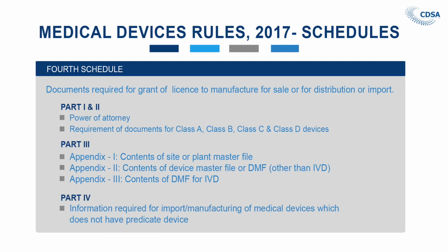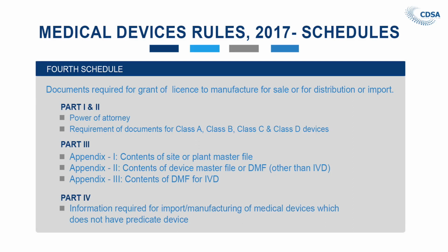What the plant master file contains is given in the Fourth Schedule, Part 3, Appendix 1. Appendix 2 is the content of the device master file for medical devices other than IVD. What content, what information, what technical document is required to be submitted as a part of the device master file for the medical devices is given in Appendix 2 of Part 3 of the Fourth Schedule. For the content of the device master file for IVD, a separate appendix is there, because the technical requirement for in vitro diagnostics is also different from the devices. So that detailed requirement has been given in Appendix 3.